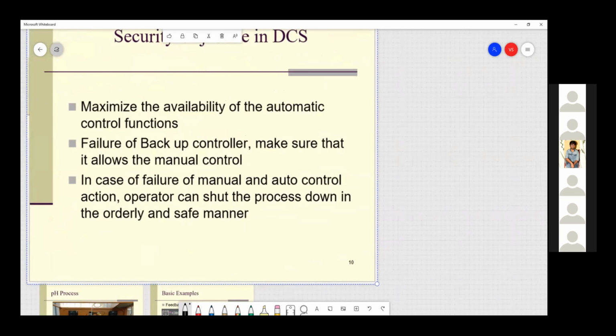The next point is, if the backup control fails, you have to make sure you can control it manually, so manual control should be there. The failure of backup control should still allow manual control. In case of failure of both manual and auto control, at least you have to shut down the process in a safe manner. That's what, in industry, people talk about startup interlock, shutdown interlock, operational and maintenance.